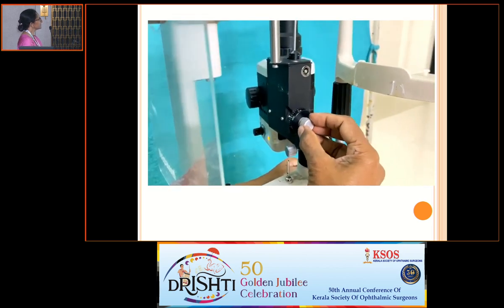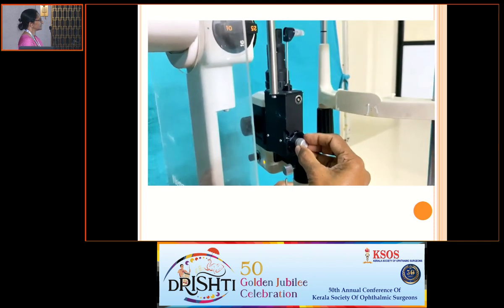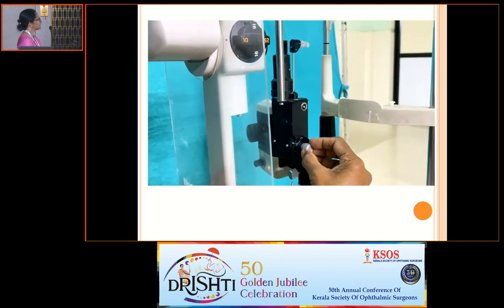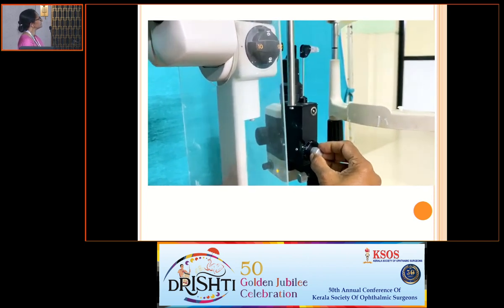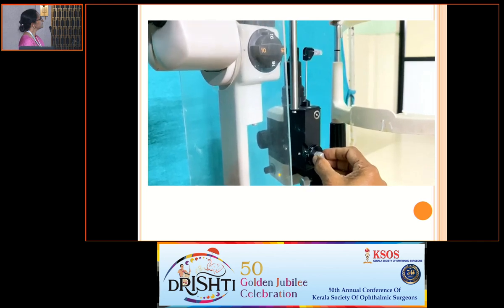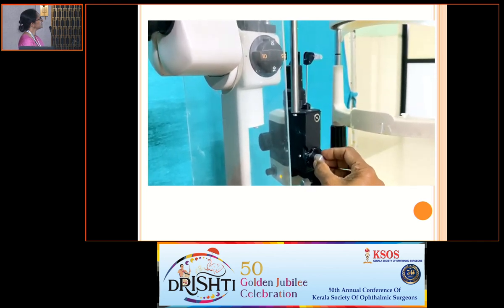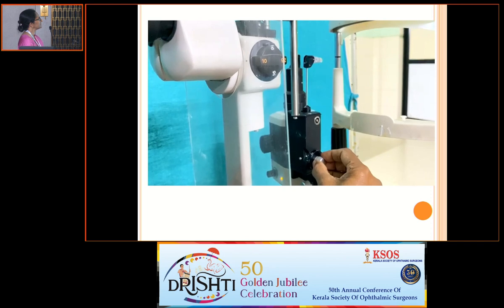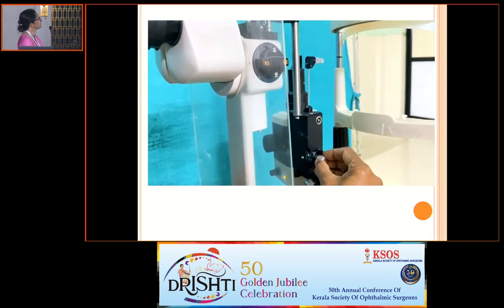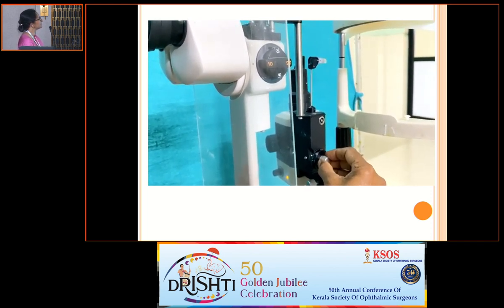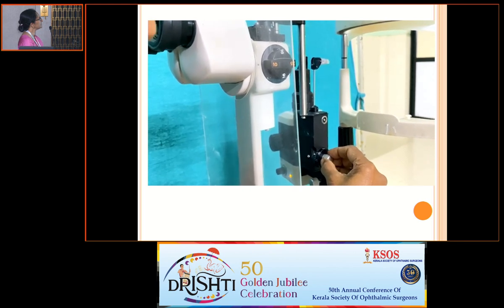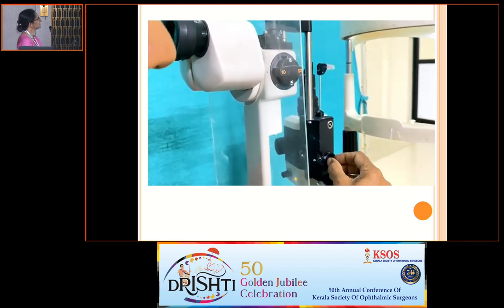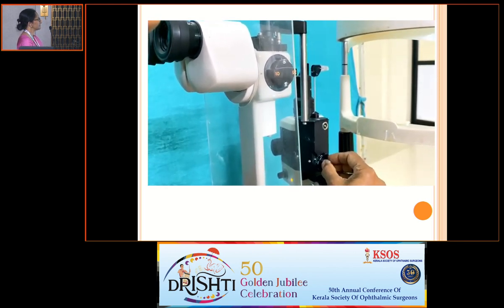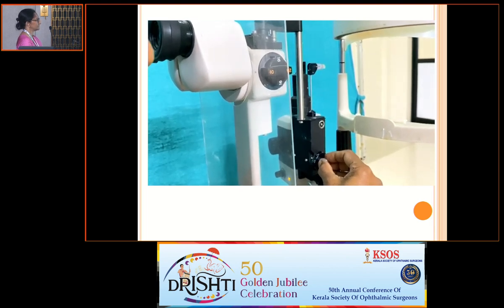Now turn the knob a little forwards, that is about 0.5 millimeters of mercury forwards, and we can see a forward movement of the feeler arm with the tonometer head. And now if we turn the knob backwards a little, that is about 0.5 millimeters of mercury, we can see a backward movement of the feeler arm and the tonometer head.